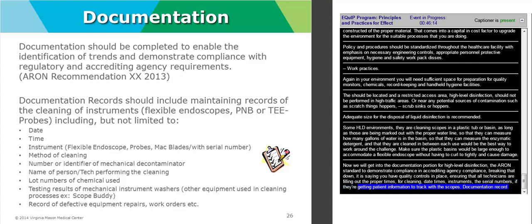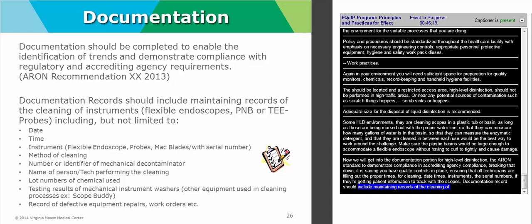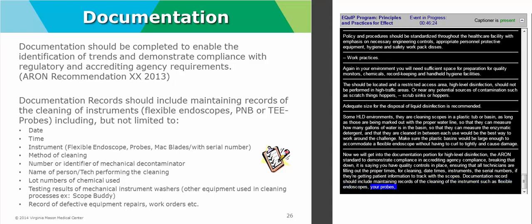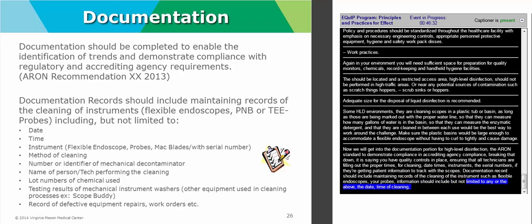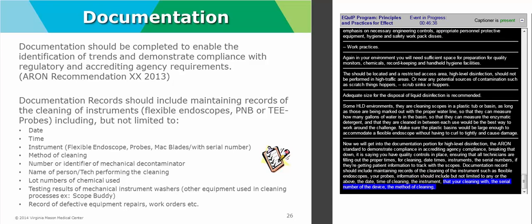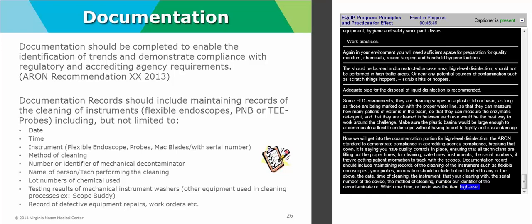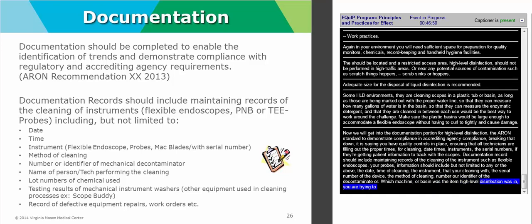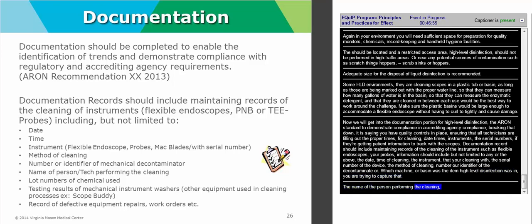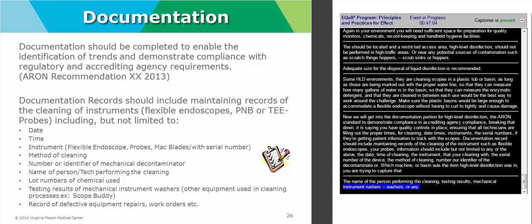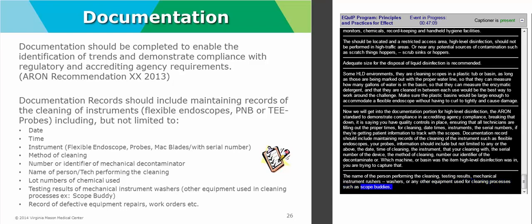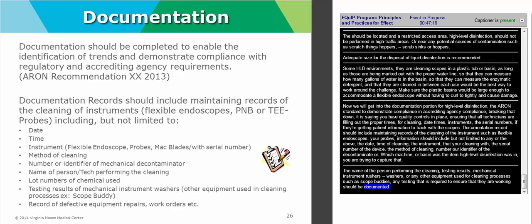Documentation records should include maintaining records of the cleaning of the instruments, such as flexible endoscopes, again, your probes, and information should include but not be limited to, so any or all of the above: the date, the time of cleaning, the instrument you're cleaning with the serial number of the device, the method of cleaning, number or identifier of the mechanical decontaminator, like which machine or which basin was the item high-level disinfected in is what you're trying to capture. The name of the person or the technician that was performing the cleaning, lot numbers of chemicals that are used, testing results of mechanical instrument washers. That would be in your decontamination area, or any other equipment that's used for cleaning processes, such as scope buddies, your AERs. If there are any daily tests required to ensure that those devices are working, they should be documented as well. And then also record of defective equipment and repairs, keeping track of work orders, and the like.